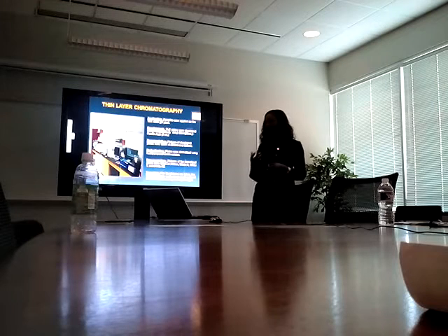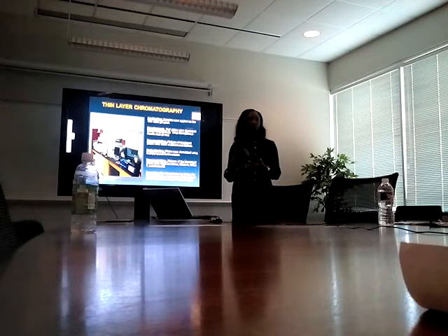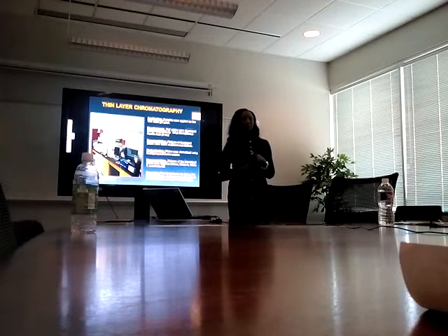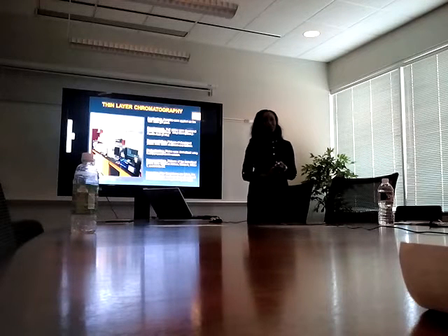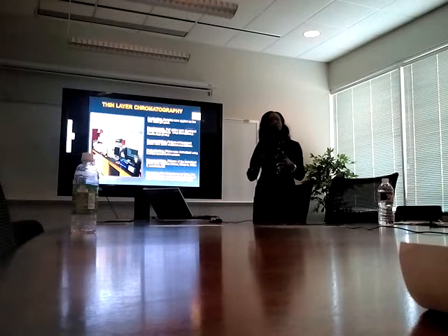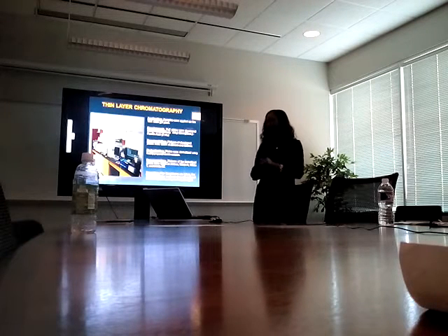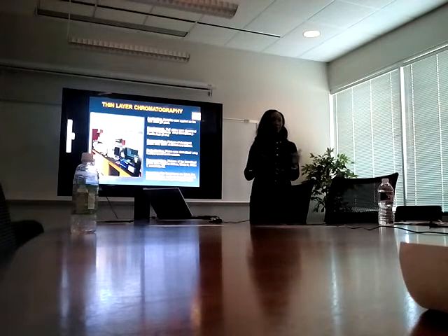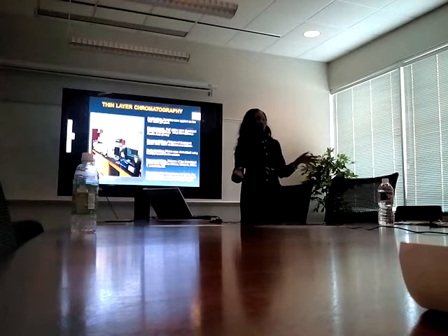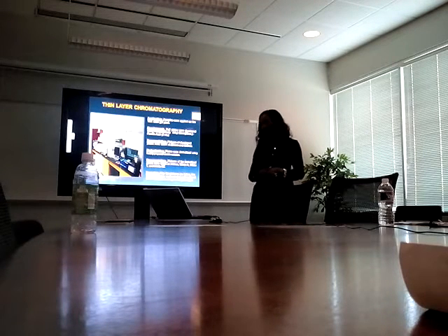We took pictures at a wavelength of 366 nanometers with the white remission light, the white transmission light, and a combination of the white remission and transmission light. After this, we also scanned the plate at wavelengths of 370 nanometers to 800 nanometers using the tungsten light.